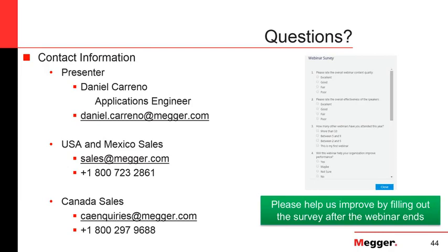And again, as for transformers, the batteries' resistance measurements are done with special instruments meant specifically for battery testing, and usually you will have, I would say, help from the instrument to measure that float current.